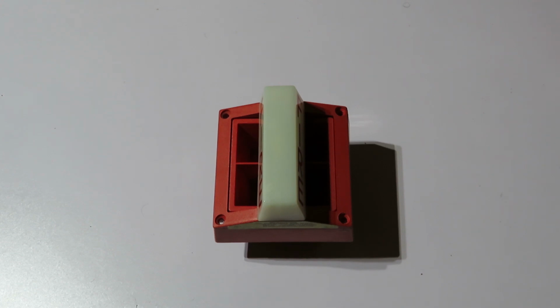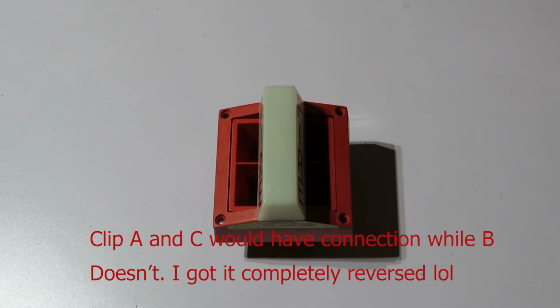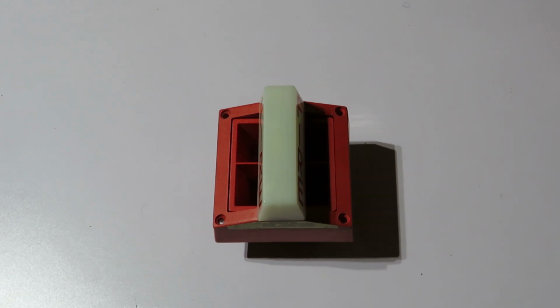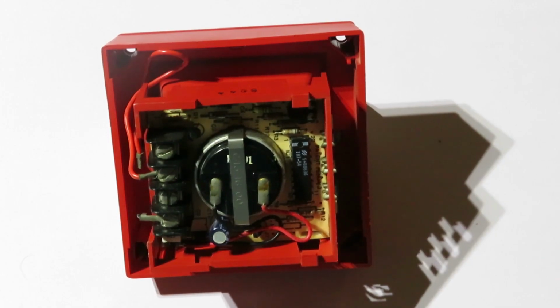Now, keep in mind, on tab to break, think in reverse. For example, break tab A would mean clip B and C would still have connection while clip A does not have any connection. And for example, say break tab B, that means tab A and C will be disconnected while tab B will have a clip in. Basically reverse. So without further ado, let me teach you how to turn this device into a selectable device. On the back, this is pretty different than other System Sensor MASS designs.